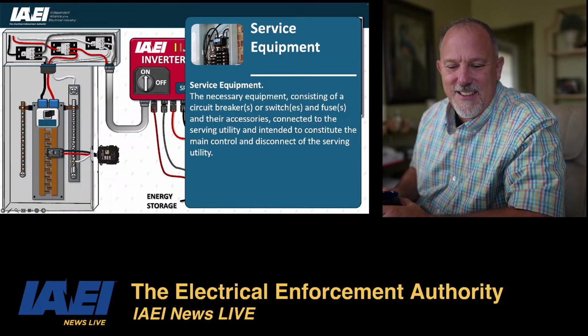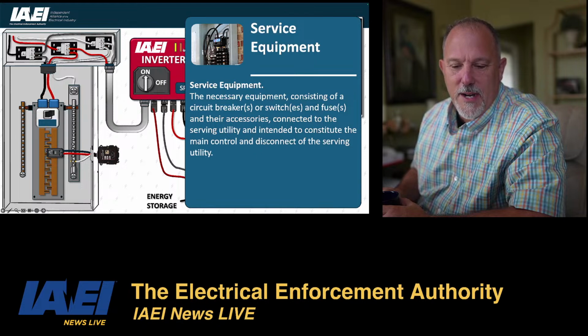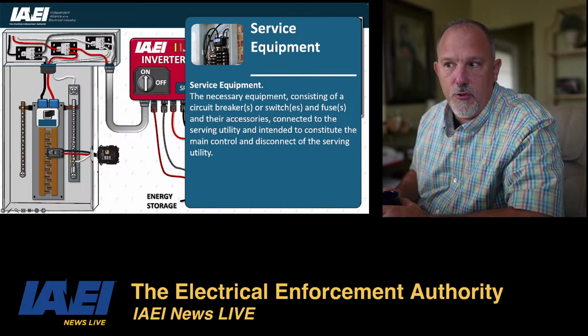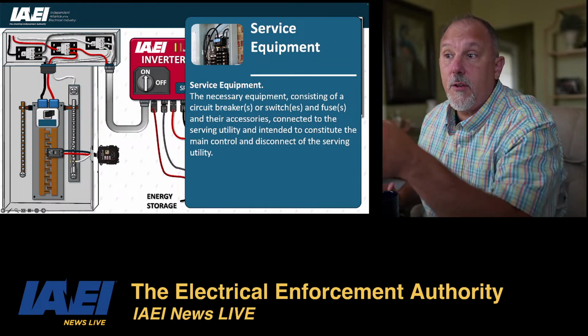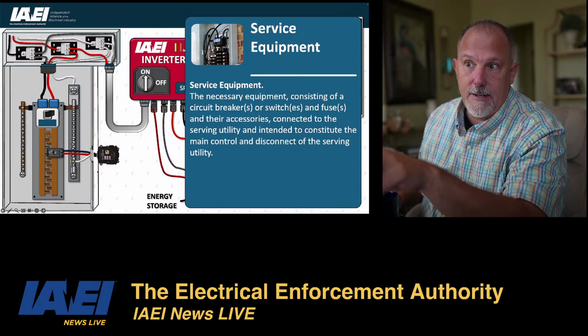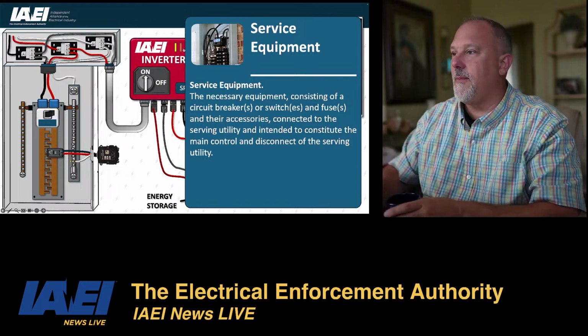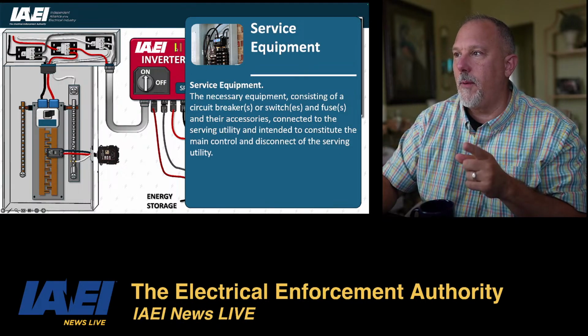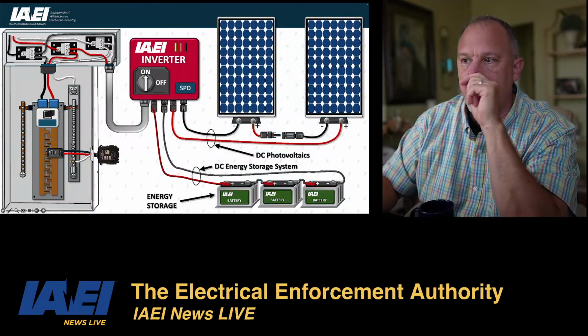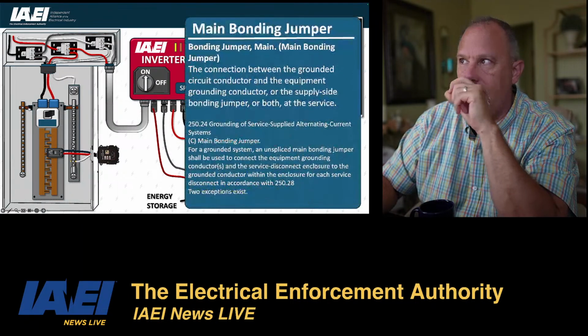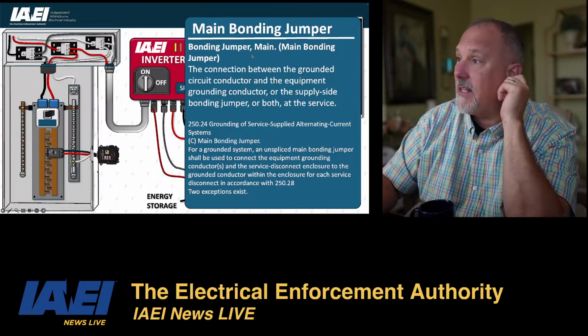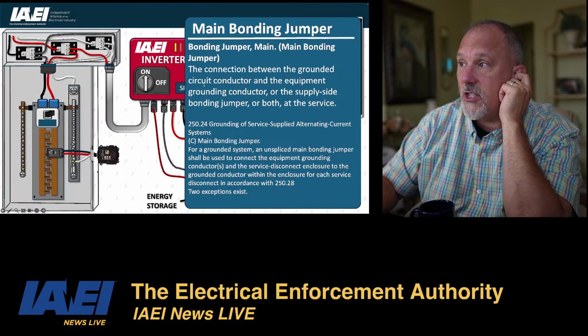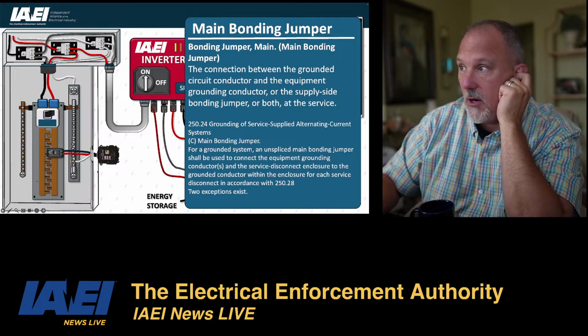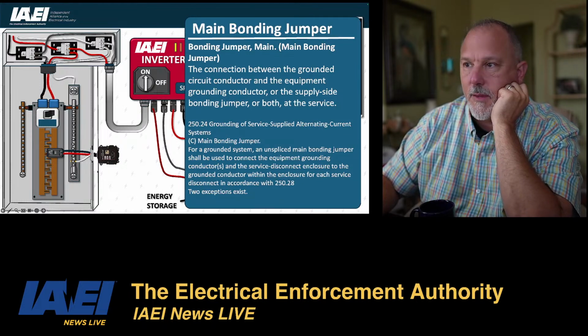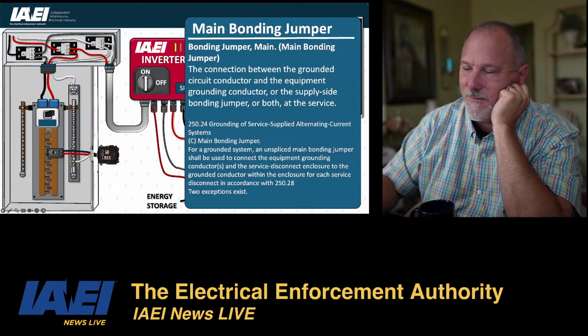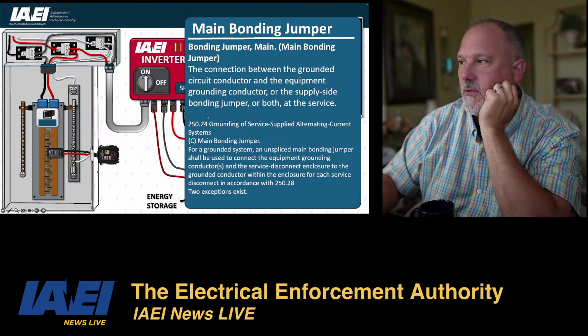Robert, connected to the terminal bar or bus, so it will not be connected to enclosure. Well, we do, right? But we do the bonding, right? There has to be a bonding jumper in, and we'll talk about that. So that is service equipment. Let's talk about this bonding. I think I have this. So the main bonding jumper is the connection between the grounded circuit conductors. So that's this grounded bar, and the equipment grounding conductor. That's this bar here, where the neutral or grounded conductor is connected.